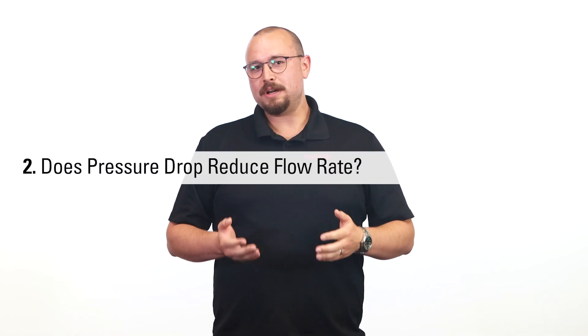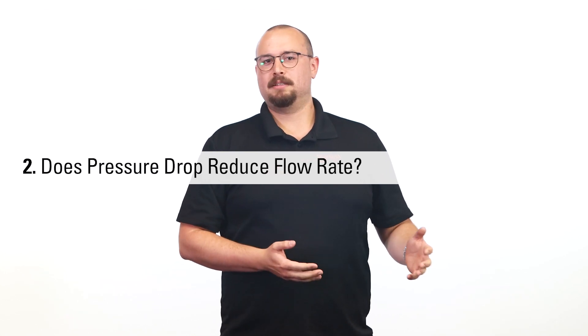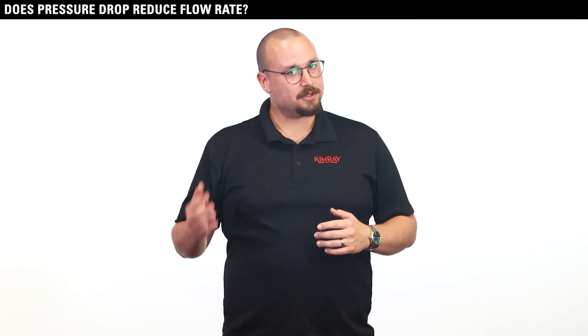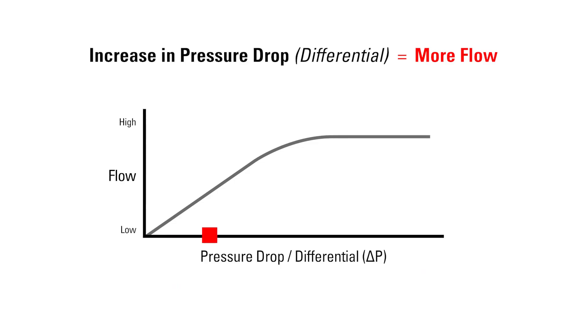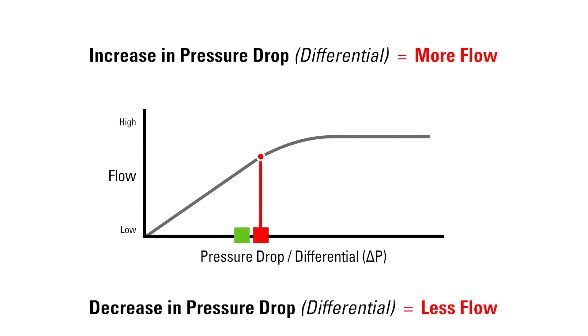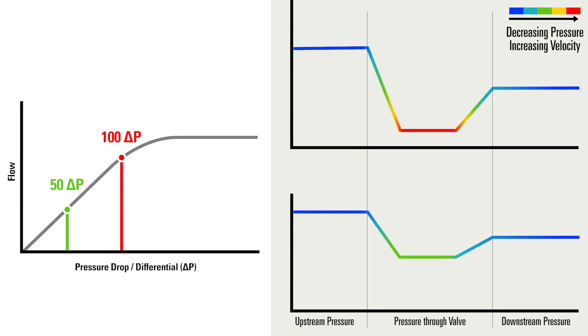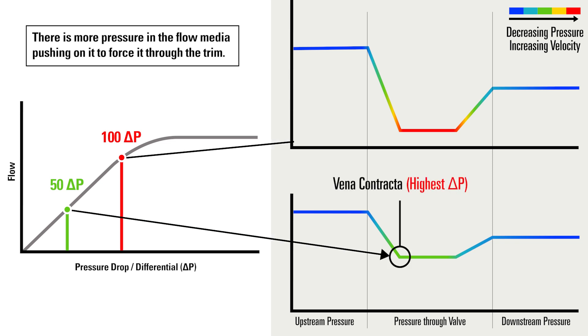Our second question is: does pressure drop reduce flow rate? Pressure drop does affect flow rate, but does not always reduce it. An increase in pressure drop or differential equals more flow; a decrease in pressure drop or differential equals less flow. For example, a valve would be able to flow more with a 100-pound drop than if it had a 50-pound pressure drop. This is because there's more pressure in the flow media pushing on it to force it through the trim.